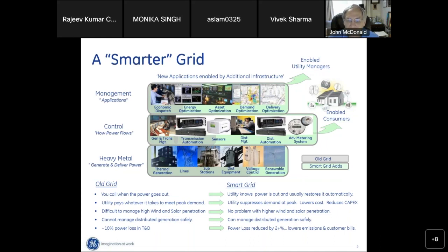Okay? And you can see at the bottom here, for instance, voltage control is shaded halfway. That means that we've been doing voltage control for a long time because voltage is directly proportional to load. Okay? When we lower those secondary voltages, we lower the load. So it's a very good way to manage load and to avoid exceeding a previous peak, especially on a hot summer day.